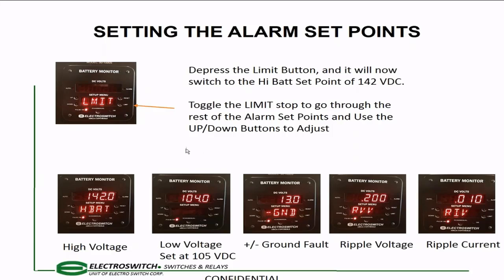So, setting alarm set points. We have this limit button on the right here. I'd be sitting there monitoring my battery. I hold the limit button down for 4 seconds, and you see my limit, LMIT, would come on. So now I'm ready to toggle up and down on the left here for setting my alarm limit.